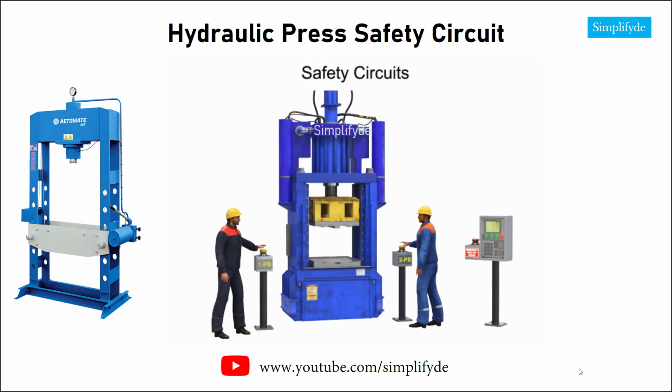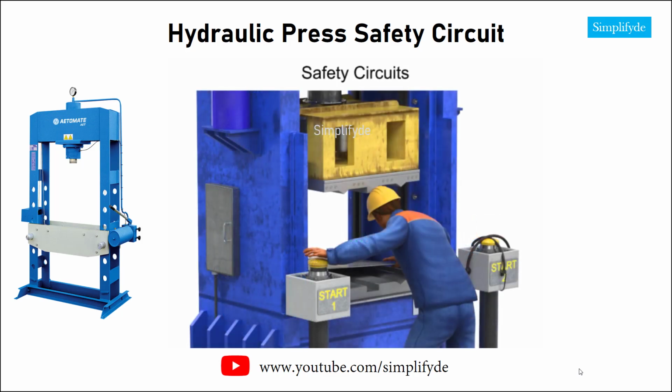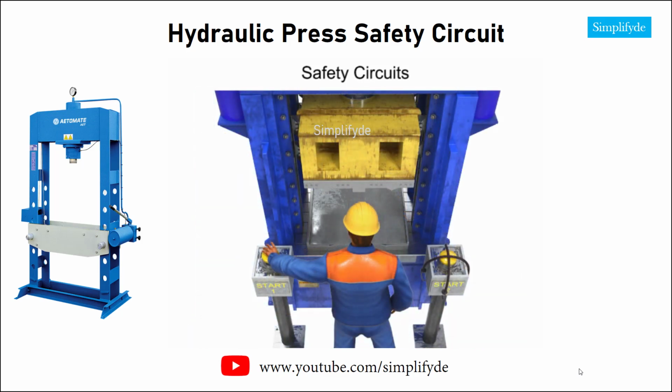While two-hand controls wired in series are ideal for machines with two operators, they become unsafe when only one operator is present. Although two buttons are still required, it becomes much easier for a single operator to tie or weigh down one button, allowing unsafe operation. To prevent this unsafe condition but still permit a single operator, anti-tie-down circuits are employed. An anti-tie-down circuit requires that the operator actuate both individual controls at the same time. If either control is prematurely actuated or continuously tied down, the cycle will not operate.